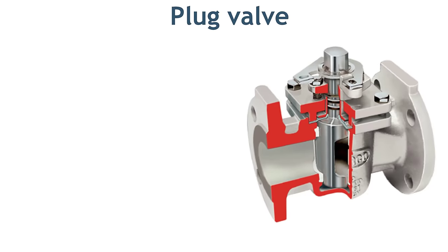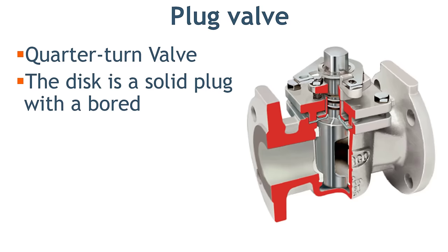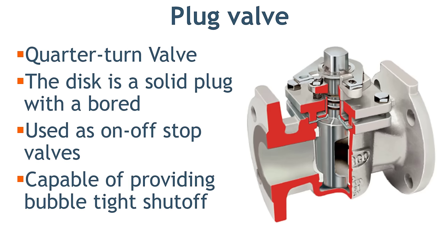Plug valve is a quarter-turn rotary motion valve that uses a taper or cylindrical plug to stop or start the flow. The disk is in a plug shape which has a passage to pass the flow. Plug valve is used as an on-off stop valve and capable of providing bubble-tight shutoff. Plug valve can be used in vacuum to high pressure and temperature applications.